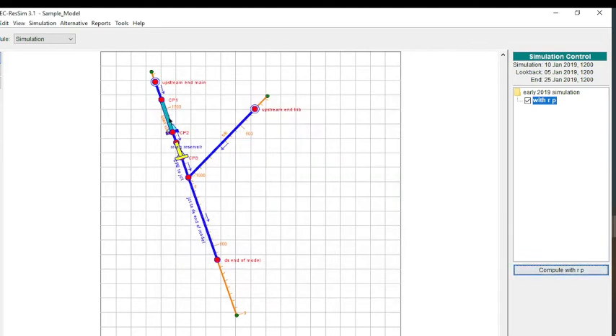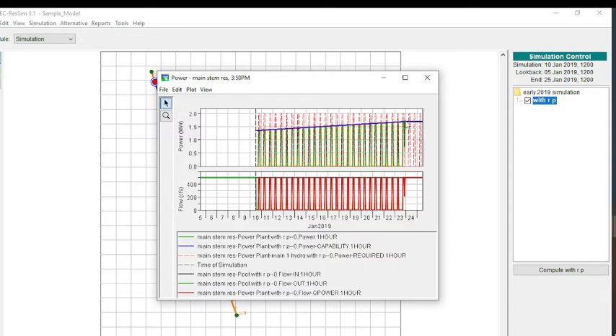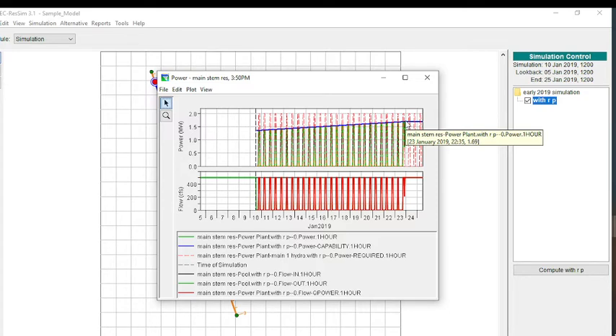We can also go look at the power that's being plotted. We'll go back to the upstream reservoir and look at the power that's being plotted. There's a few things going on here. One is the blue line is showing the capability that we have. The capability goes up as the pool elevation goes up. Capability would increase as either the pool elevation goes up or the flow goes up.